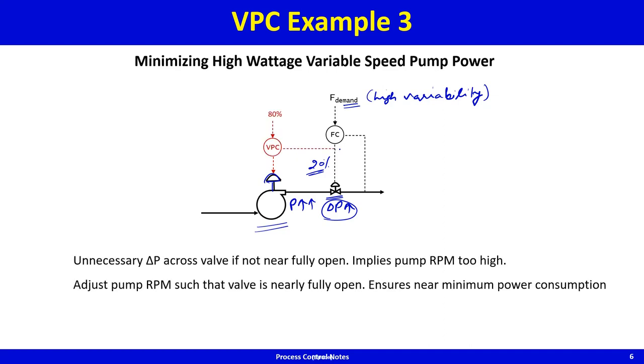A smart operator measures the valve position and, if it is not say 80% open, reduces the RPM. You have a valve position controller that compares the valve position with a nearly-fully-open set point. If the valve is less than 80% open, the VPC reduces RPM. If the valve position goes above 80%, RPM is increased — so this is a direct-acting controller.